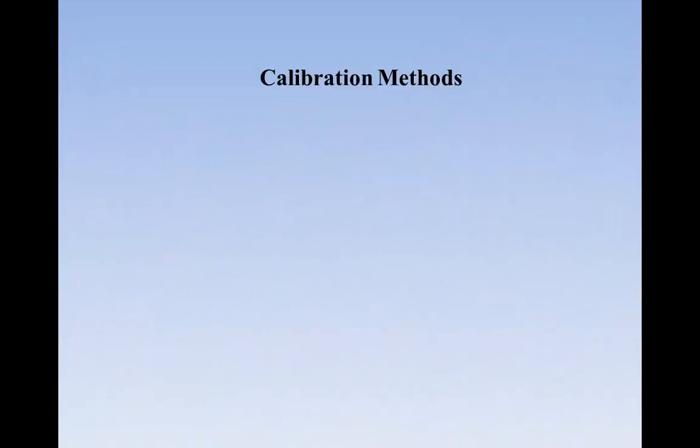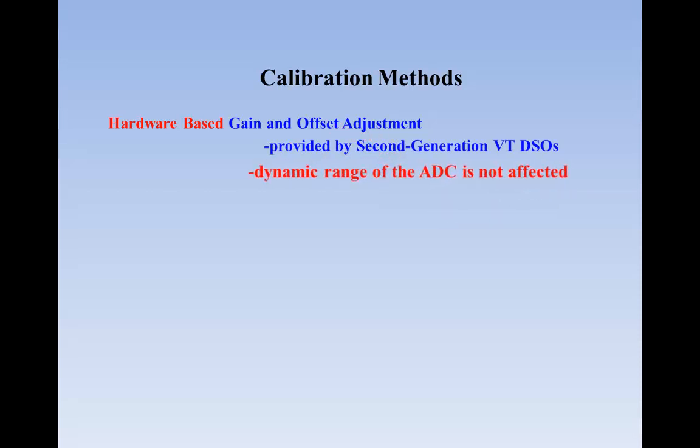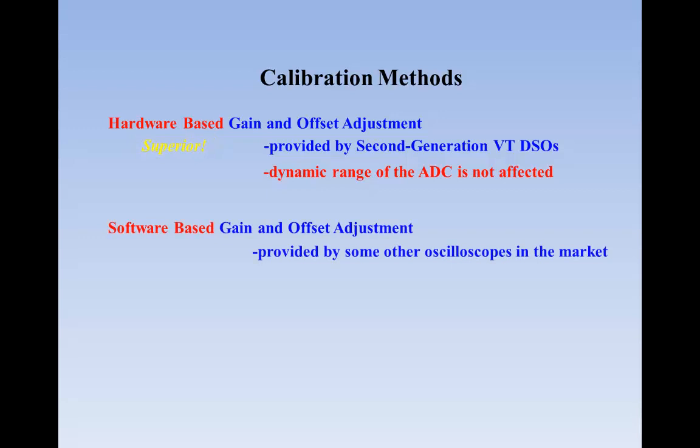Unique Feature 10: Calibration and recalibration. All the second-generation VT DSOs are individually calibrated to the specifications. This results in higher accuracy than their peers without additional cost. Some models allow the user to recalibrate them using the built-in signal generator. These models are equipped with independent gain and offset adjustment hardware. As the adjustment is done before ADC, the dynamic range of the ADC is not affected. This is superior to the software gain and offset adjustment method used by many other oscilloscopes in the market, where the adjustment is done after ADC and thus the dynamic range of the ADC is adversely affected.